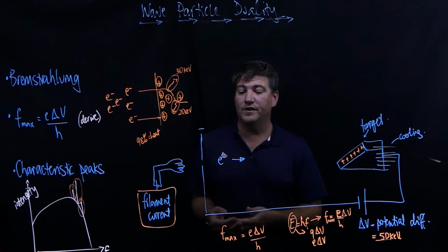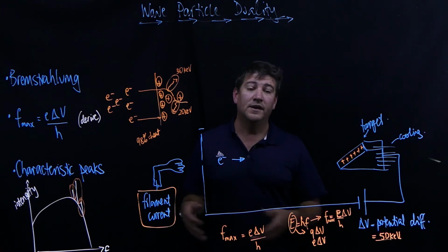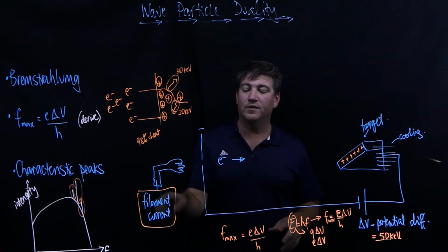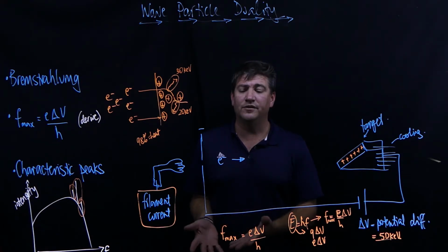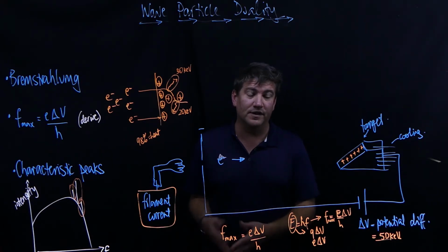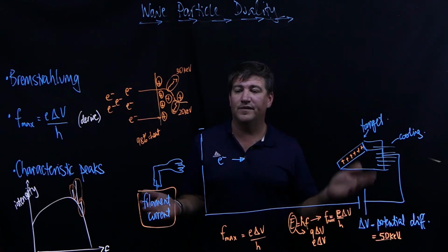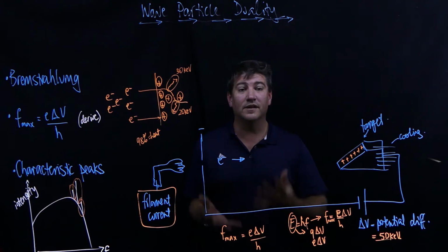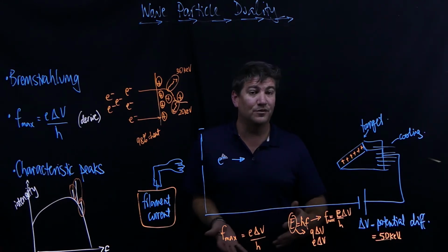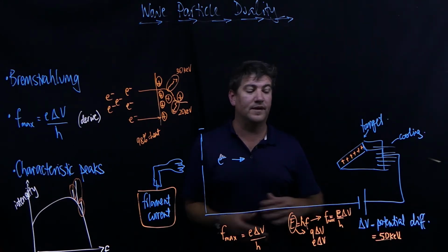This might be useful if you have a small child in pain, they've broken their ankle, and you want to get the job done nice and quick, so you might wind the filament current up a little bit. It could be that you have a patient who's had lots and lots of X-rays in the past because they've had surgeries and whatever. You might wind the filament current down, so you've got less chance of doing damage to their soft tissue with the electrons as they interact.